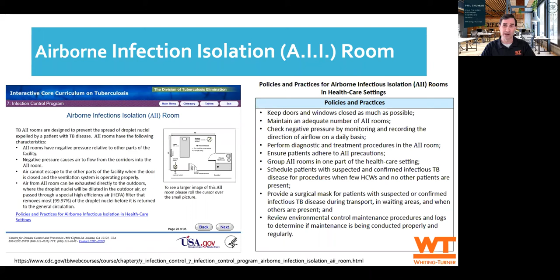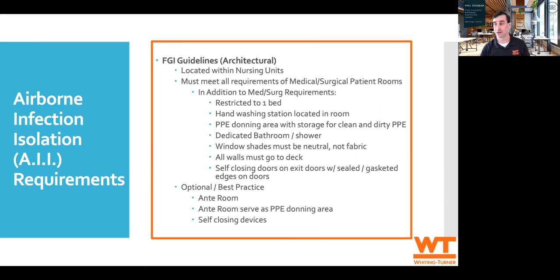Architecturally, we face requirements that every patient room have its own bathroom, the recommendation of having an anteroom for every AII room, and converting double occupancy patient rooms to single occupancy. While newer hospitals are usually designed with the single patient model in mind and many have bathrooms, older facilities face challenges to add these items while maintaining the required square footage for a patient room, and also not encroaching on the corridors. Slide, please.